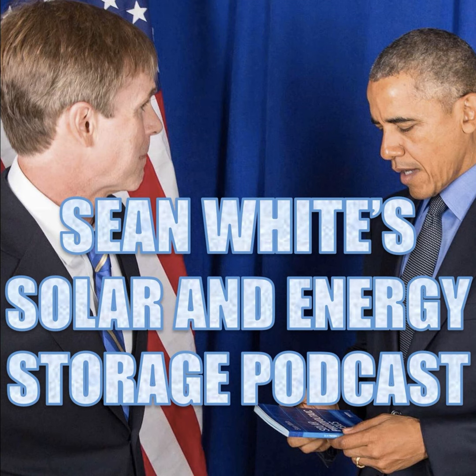Yeah, we certainly do. There's also a standard, NFPA 855, the standard for energy storage systems. We go through extensive testing and certification to make sure our systems adhere to that. At Fluence, safety is one of our core values, and we were one of the first to come up with not just the large scale fire test but what we call the beyond fire test, which takes it further. We actually ignite an entire enclosure and ensure it goes into full thermal runaway, proving that it doesn't propagate to the enclosures next to it.